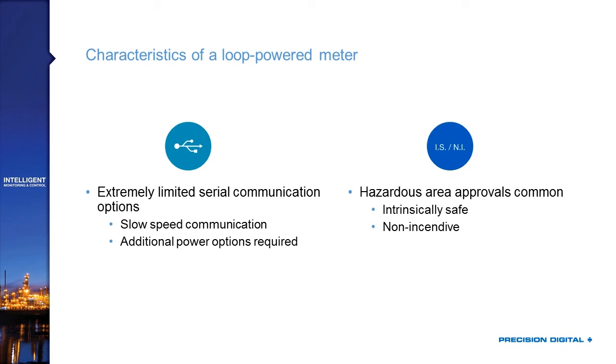On the plus side, hazardous area approvals are pretty common on loop-powered devices. Most manufacturers will have either all of their loop-powered devices approved or all of the ones in a particular series, or sometimes they'll have an approved version and a non-approved version of the same device. Because loop-powered devices do have that low-power nature, it makes it fairly easy to get intrinsically safe and non-incendive approvals on it for use in hazardous areas.